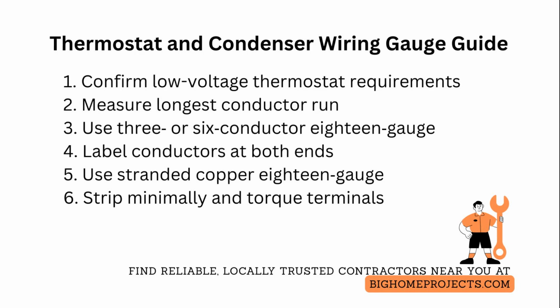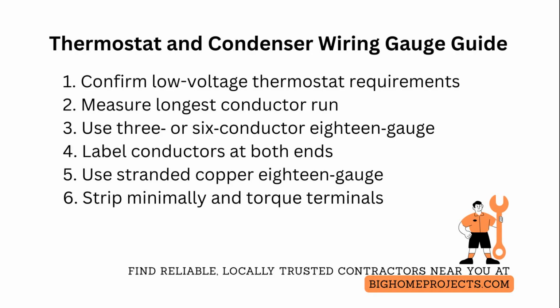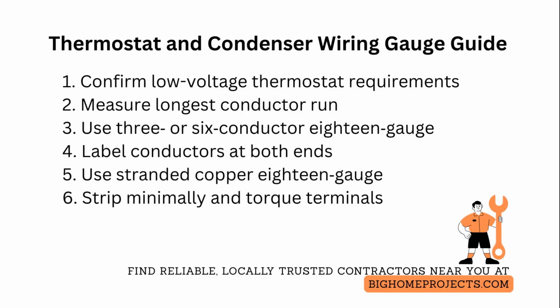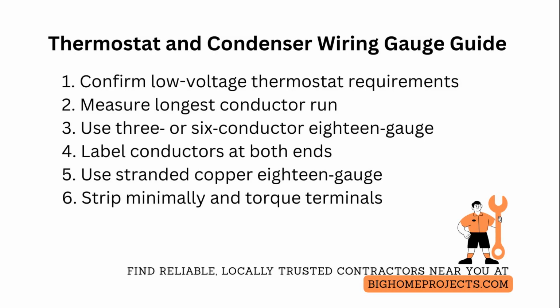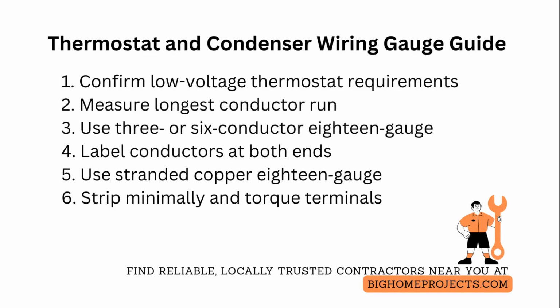For long runs, calculate voltage drop. For control signals, a small drop can still cause read errors. If you exceed allowable drop, upsize to 16-gauge or run a dedicated 24-volt transformer closer to the thermostat location. Grounding and shielding are unnecessary for standard low-voltage thermostat circuits unless you have significant electromagnetic interference. If you do, use twisted pair or shielded cable and bond the shield at one end only.